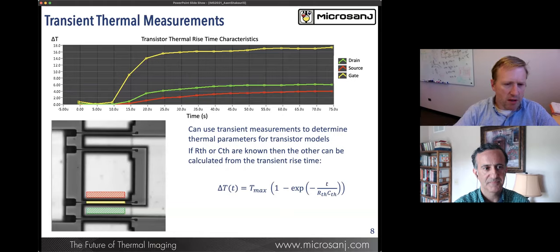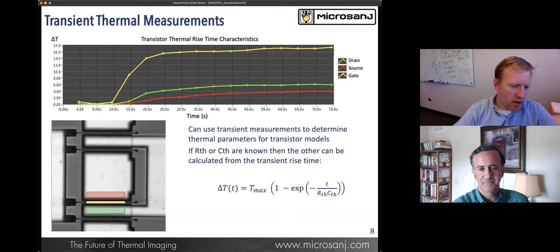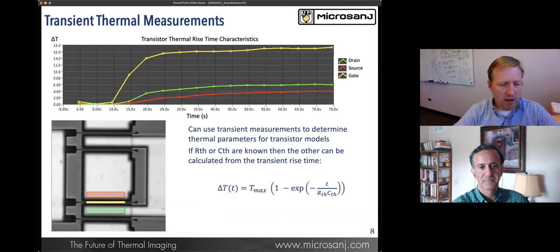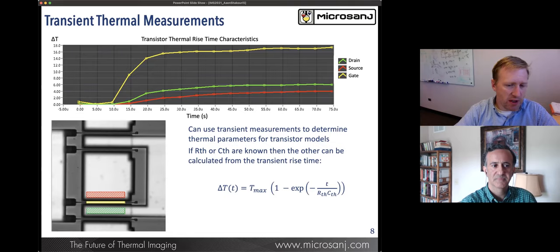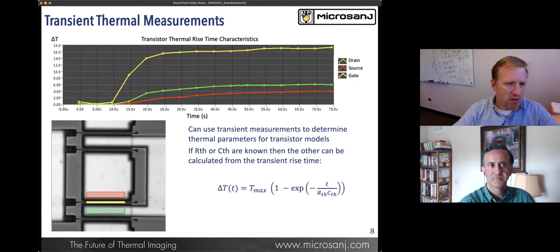What we can do now with the Microsanj system is we can determine areas of interest where we want to see the temperature. In the bottom left hand corner here, we have three areas - they can be individual pixels, or you could have an area where you could look at all the pixels simultaneously. We're able to pick out the overall temperature within that area of interest.